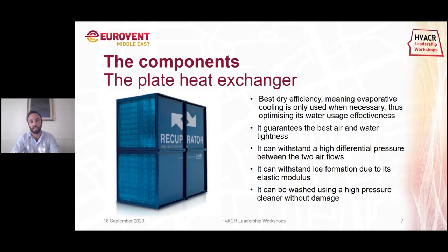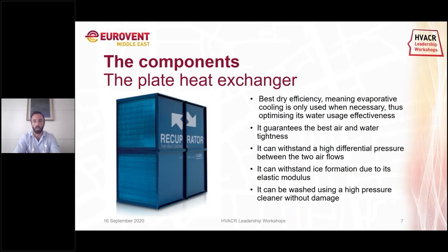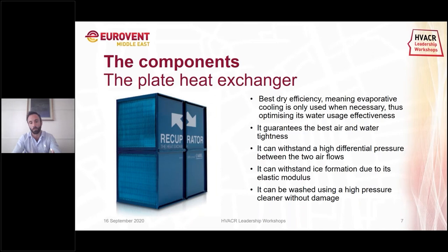The plate heat exchanger has the best dry efficiency, which translates into the best adiabatic cooling performance. The evaporative cooling solution can be used when needed — when the outside temperature is too warm to use just the dry performance of the heat exchanger. Another key point is that it guarantees the best tightness between the two airflows, meaning the indirect evaporative cooling technology can keep the absolute humidity of the supply air constant — we are not modifying the absolute humidity of the supply air.